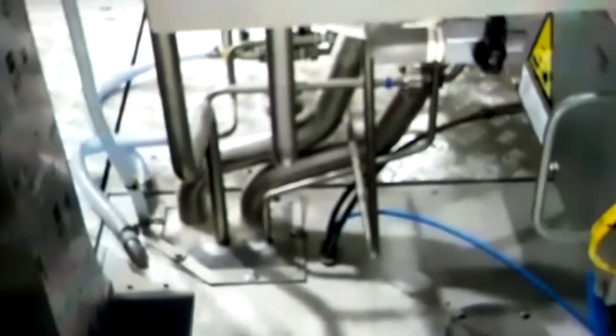On occasion, I've seen it happen where this pump has failed here, and these actually melted. They actually melted the pump because of high temperature. So now this is extra to guard if we have no flow. So now this came on extra. If you look over there, we have that white container. Yeah. This is the primer, the priming section for all of this. We'll go back around the other side and have a look. But that's where we prime the water for here. There's a drain valve here. Okay, this one. So don't bump this, otherwise the water will all drain out.